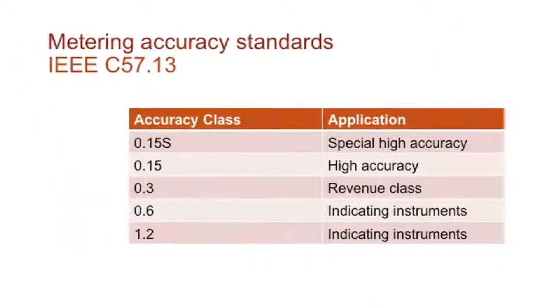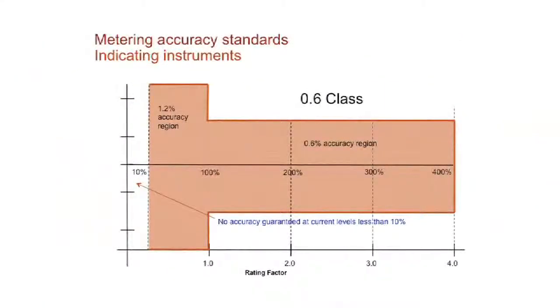Okay, first, the IEEE has very, very distinct definitions for metering accuracy. And so let's go over those right now. If we start from the bottom going to the top, which will be the least accurate going to the most accurate, there is an accuracy class of 1.2, and there's also an accuracy class of 0.6. Those are both indicating instruments.